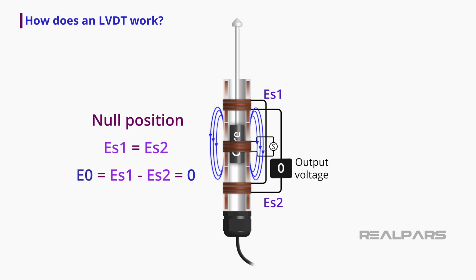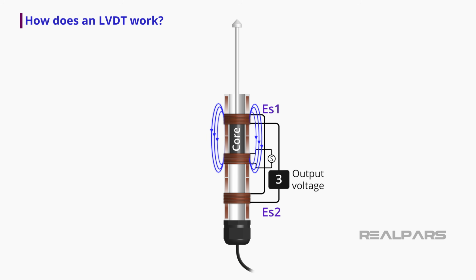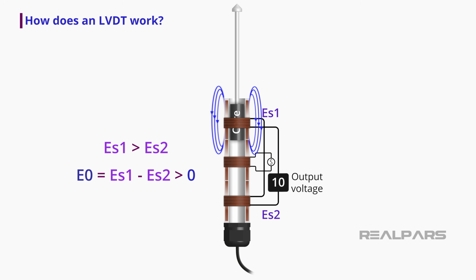We know that they are electrically 180 degrees out of phase with each other. Therefore, they will cancel each other, and the output voltage will be zero. This characteristic is used when calibrating an LVDT sensor. As the core moves from this null position, the net induced voltage changes. When it moves upwards, the induced magnetic flux on the upper secondary winding is greater than the induced magnetic flux on the lower secondary winding. This results in a positive output voltage.